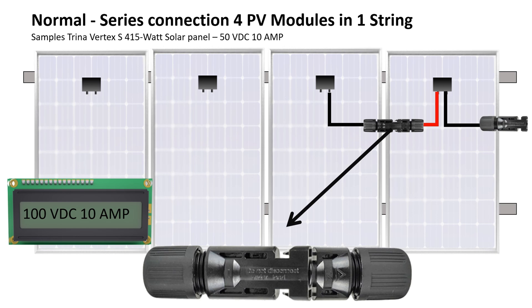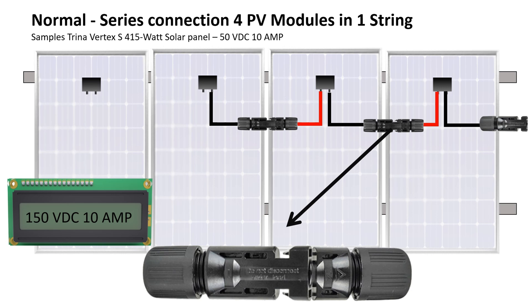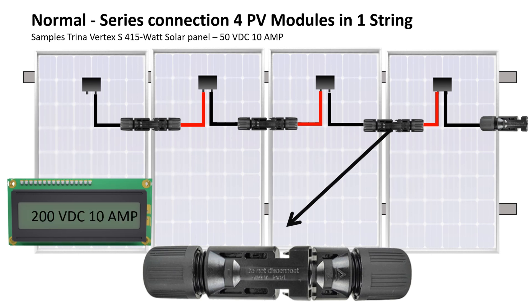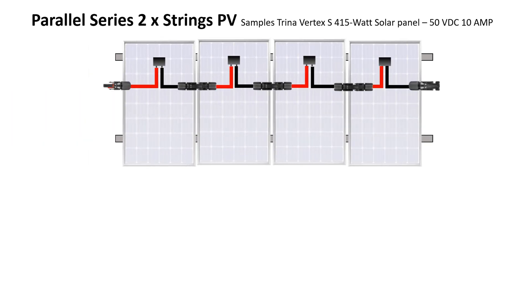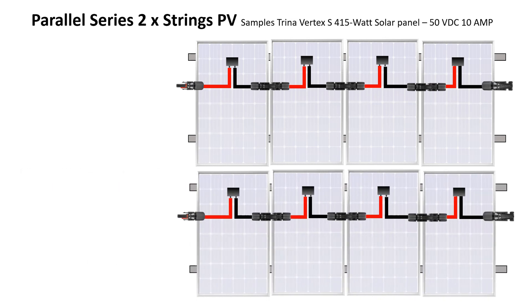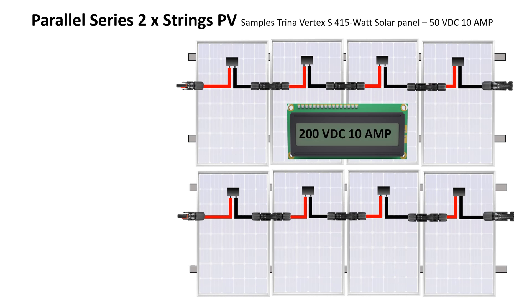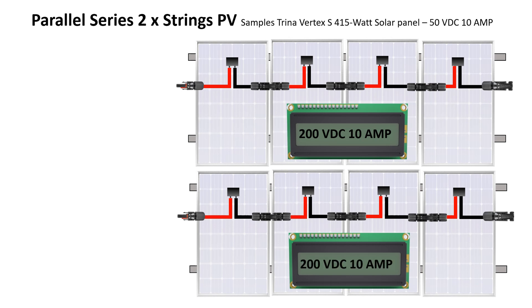As soon as you connect the next panel it becomes 100 volts but stays at 10 amps. Add the next panel and it becomes 150 volts DC at 10 amps. Keep connecting to the end of the string and you get 200 volts DC at 10 amps. For a parallel setup, you put a second string of the same panels alongside the first — each string giving you 200 volts DC at 10 amps.